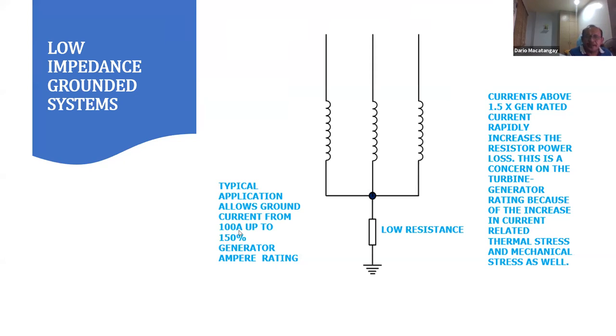When you're dealing with a generator, the CT ratio is very high. The generator is typically in the range of 1,000 or 2,000 amperes. If it is 2,000 amperes, you would need a CT primary rating of more than 2,000 amperes, so let's say 3,000:5. So 3,000 divided by 5 is 600:1.